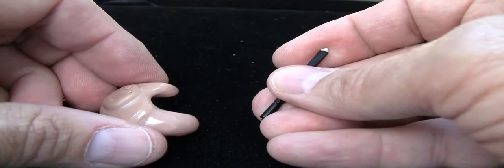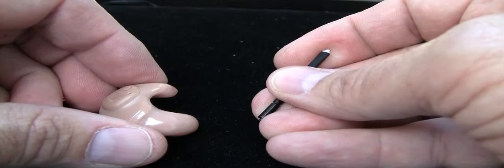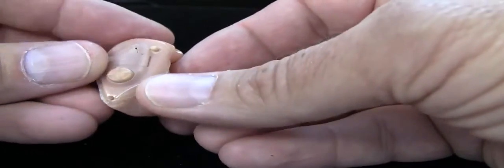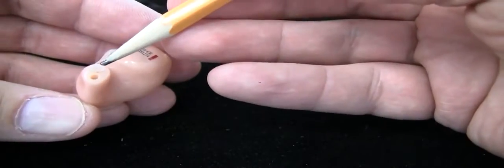If we do all these troubleshooting things and the hearing aid still does not work, then we will send it in to the laboratory and they will recondition the hearing aid. When it arrives at the laboratory on an in-the-ear hearing aid, the technician will actually take a razor blade and go along the edge of the hearing aid and open it up to get access to the components. Typical problems with hearing aids are the microphones being full of debris or defective, and also the receiver, which is where the sound comes out.